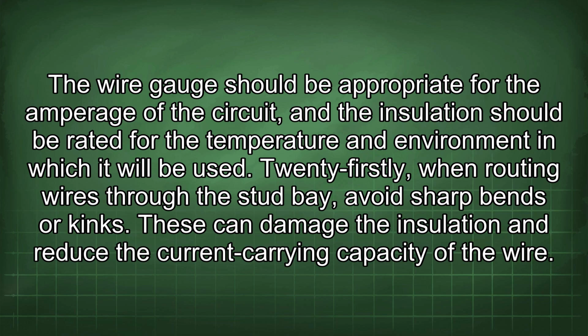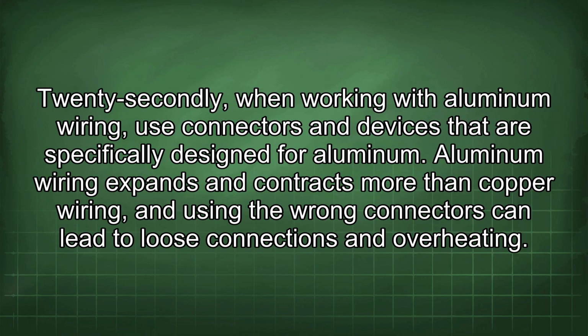21stly, when routing wires through the stud bay, avoid sharp bends or kinks. These can damage the insulation and reduce the current carrying capacity of the wire. 22ndly, when working with aluminum wiring, use connectors and devices that are specifically designed for aluminum. Aluminum wiring expands and contracts more than copper wiring, and using the wrong connectors can lead to loose connections and overheating.